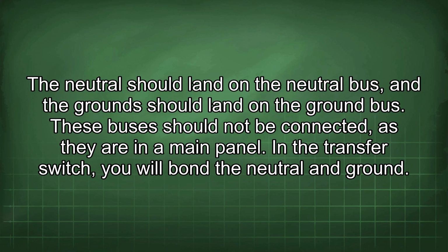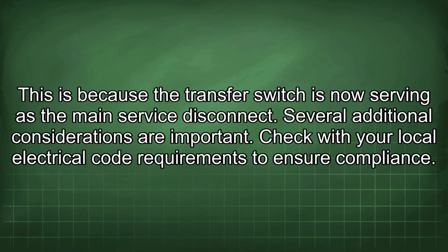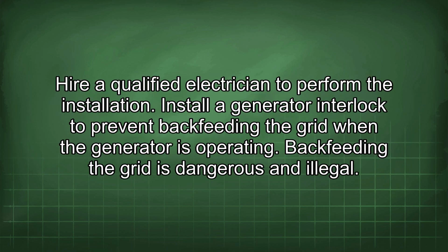These buses should not be connected, as they are in a main panel. In the transfer switch, you will bond the neutral and ground. This is because the transfer switch is now serving as the main service disconnect. Several additional considerations are important. Check with your local electrical code requirements to ensure compliance. Hire a qualified electrician to perform the installation.